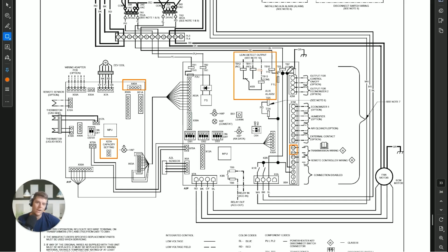You also have your other wires here, which is your high voltage in that comes through 24 volts from your transformer. I say high voltage, that's not high voltage, that's coming in from another side there. This is your low voltage, right? This is your normal low voltage that powers this board. Again, nothing crazy here from what I can see, from what I can tell. You know, you've got your communication, you got your DS1, DS2, DS3, DS4, your learn button. This is a lot like the board that you see in the Daikin Fit.